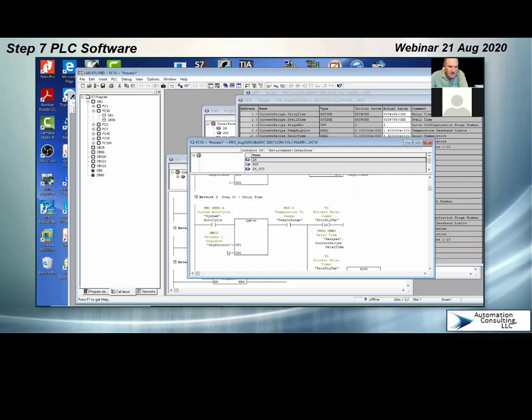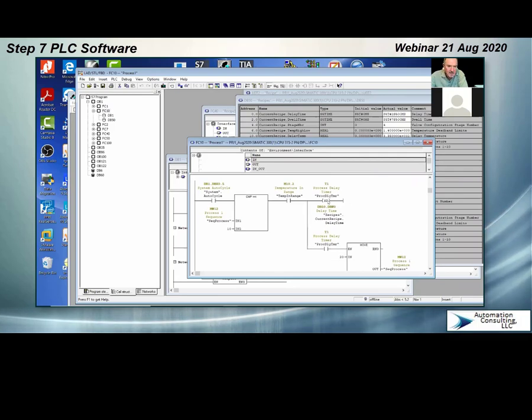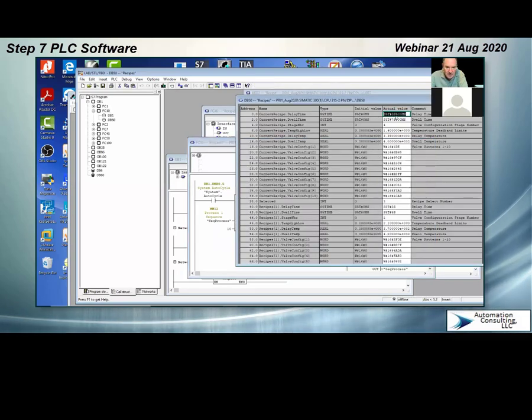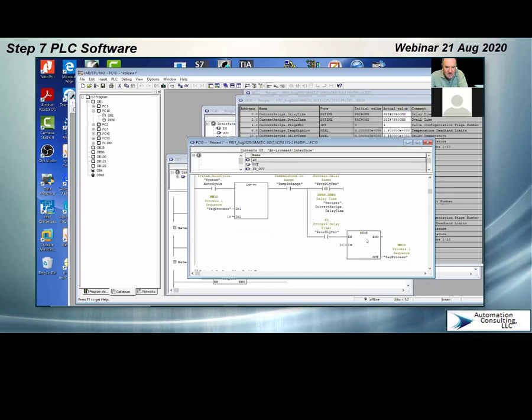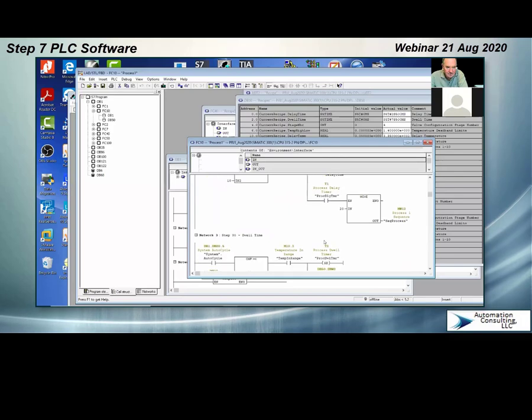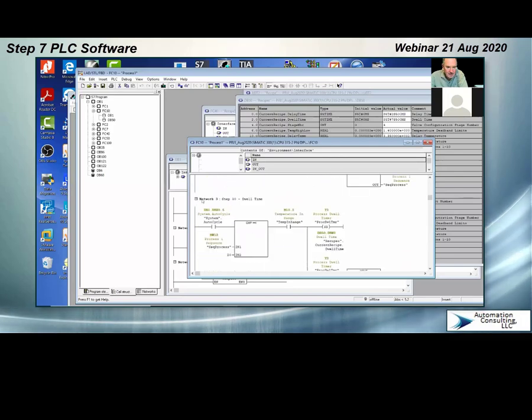If I'm in auto cycle and I'm in step 10 in this sequence and my temperature is in range, then I run a timer. The timer's set point is that delay time that we did up here, right? This delay time. So there's my 2.5 seconds. It should run 2.5 seconds after its temperature is in range. Once the timer is expired, I move a 20 and I'm now in the 3rd step. So here's step 20.